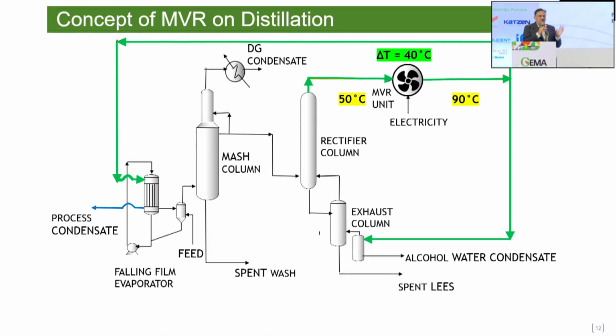So apart from using MVR on the evaporation section and also the drier vapors, we now use an MVR also in the distillation plant. The vapors coming out of the rectifier column are passed through an MVR, which is an alcohol MVR, compressed and then reused back in the mash column as heat input. With this, we are able to achieve a very low steam consumption of about 1.7 kg per liter in the whole complex of an ethanol plant.